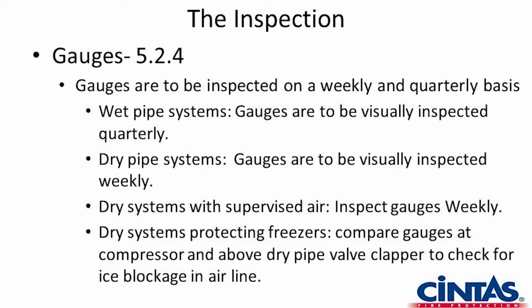They are to be inspected on a weekly and quarterly basis. They're also looked at on the annual. The weekly inspection, you are going to have us out every week to go look at gauges, but that is definitely something that is looked at on a quarterly basis. We encourage property owners to have a checklist for weekly inspection of their extinguishers and their water gauges and things like that. For E-lights, the push button, all those are planned maintenance items that are handled with the maintenance engineer or maintenance department for a facility.